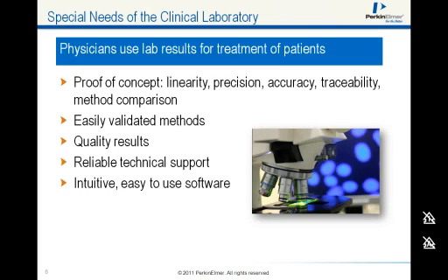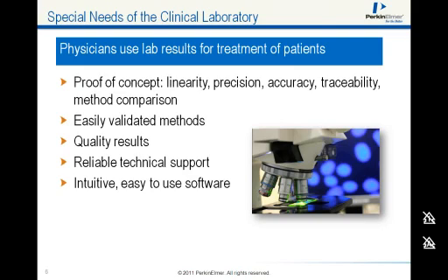Physicians use lab results for treatment of patients, so data needs to show good linearity over the clinically relevant range, precision with within-run and between-run percent CVs, accuracy, and recovery from spiked samples. There must be traceability to standard reference materials and certified methods like NIST SRMs, and comparisons to known existing methodologies like immunoassay and MS-MS. Clinical labs will consider systems that can be easily validated based on proof-of-concept data and quality results with no ambiguity, and require reliable technical support to maximize uptime and avoid downtime.